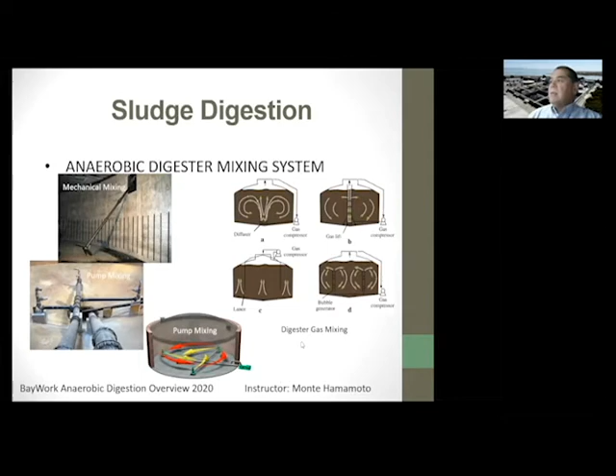There are three main operating controls of a digester. If you talk to any operator, they go, well, digesters are kind of a black box, because you can't go in and see what's inside of it because it's all sealed, and you just kind of guess what's happening in there based on the lab results that you get out and how much gas you're producing. But the three different things that the operators have control of to make sure that the digester is operating properly are keeping the temperature at 95 degrees, heating it; feeding it, so how much food you're putting into it; and then mixing. You maintain good contact with the food and the microorganisms.